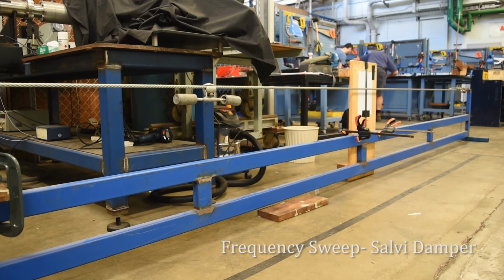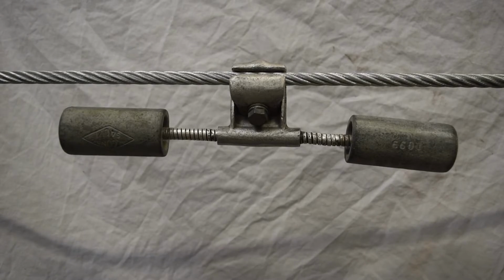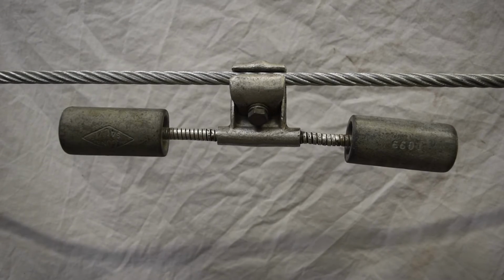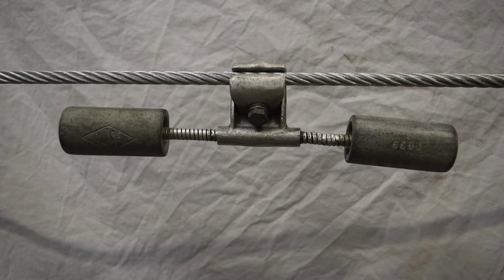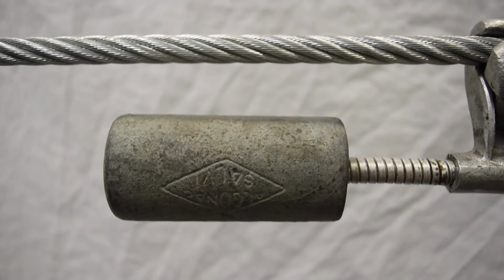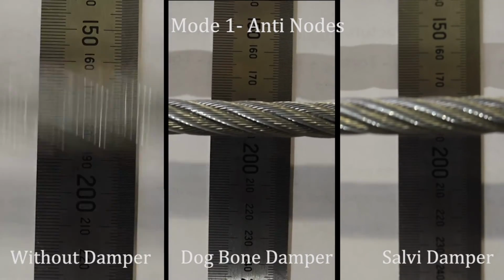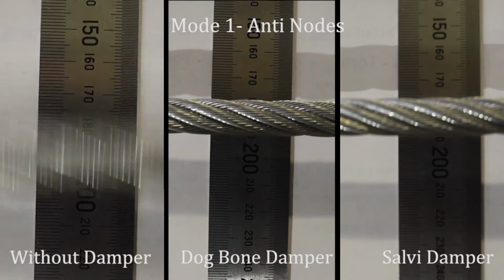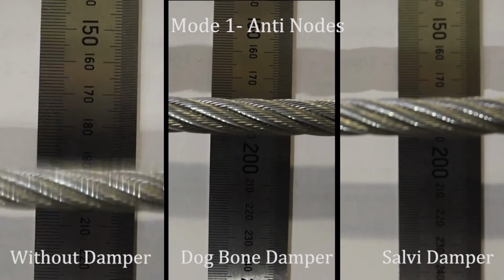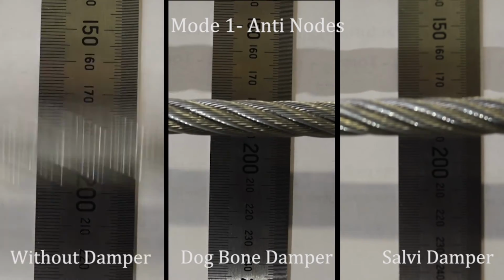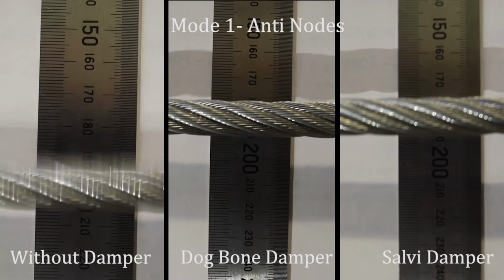With the Salvi damper attached to the cable, another frequency sweep was performed. The amplitude of vibration has again been significantly reduced. The largest response in the damper occurred at about 10 Hz. This vibration is shown on the screen here. Finally, here's a comparison of the antinode vibration at mode 1 between the damped and undamped systems. As you can see, the dampers have worked effectively to reduce the vibration in the cable.